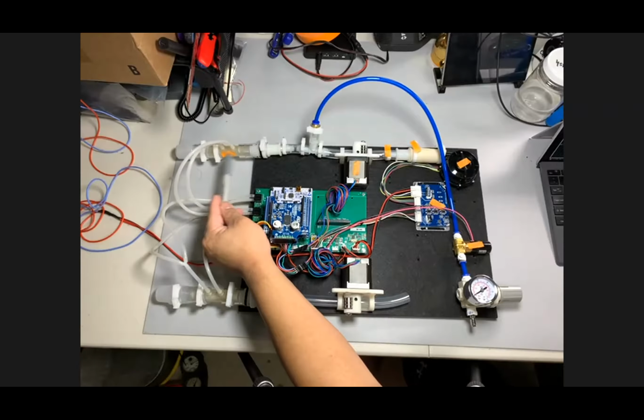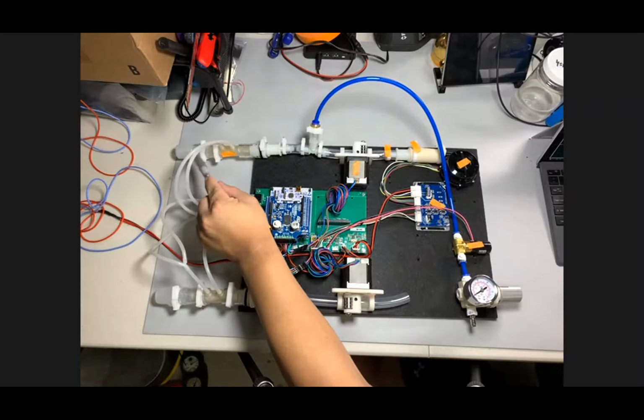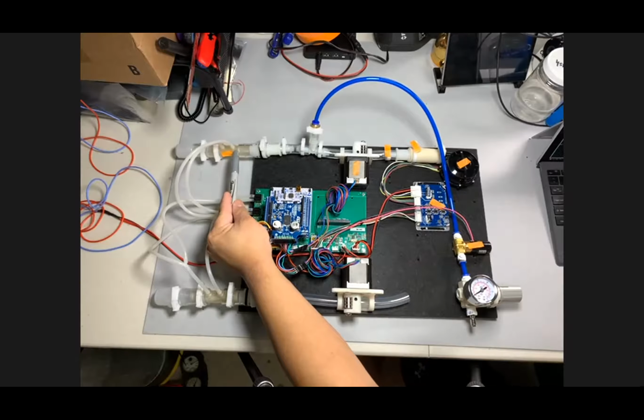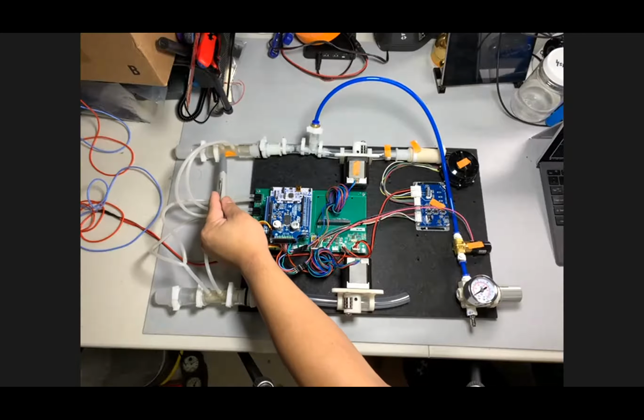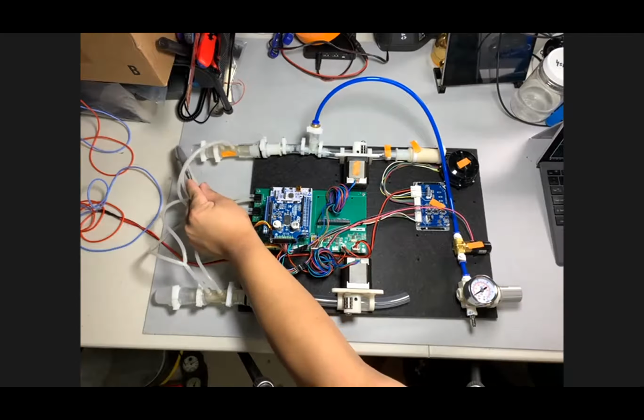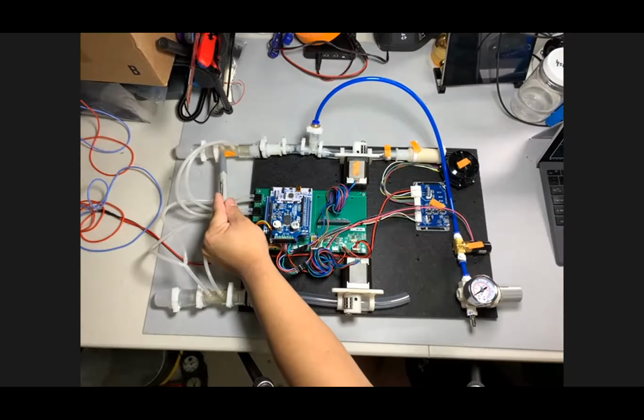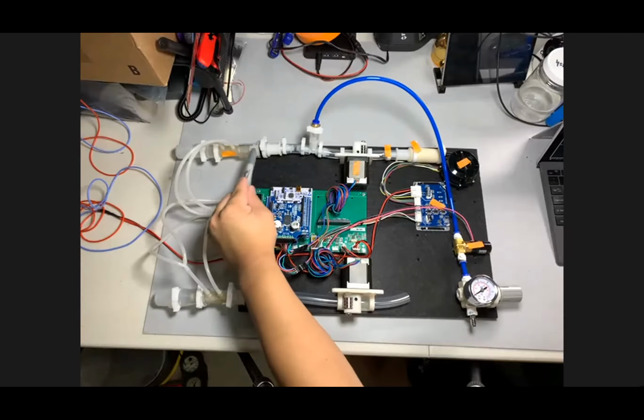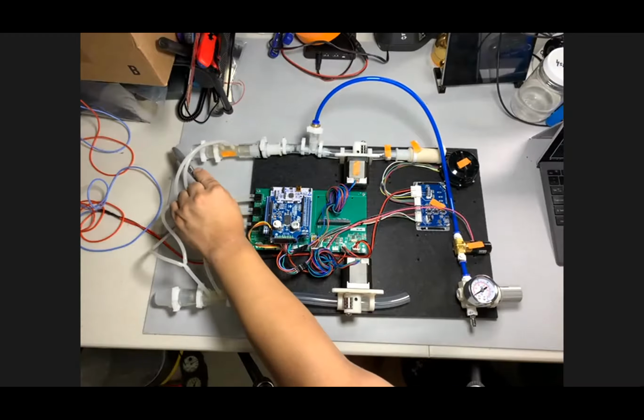So this pressure here is slightly higher than this pressure here, and this is the side that the patient sees. Now on this side, this is the source pressure tap off, right, which is being compared to the venturi vacuum. So because there's this drop here, and because of the venturi effect creating the flow dependent vacuum on this port here, neither of these pressure sensing points is at the patient's pressure, which is out here. This one because there's a vacuum created by the venturi, and this one because it's upstream of that restriction. So the pressure here that's being sensed by this line, it's sensing the pressure essentially in this limb and not in this limb, which is going to the patient.